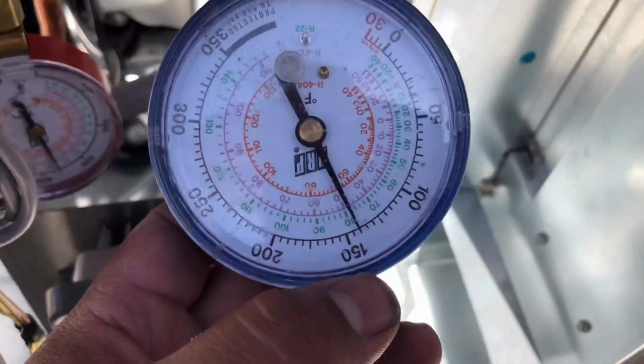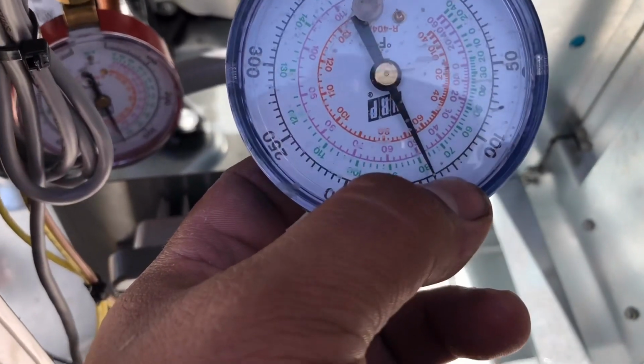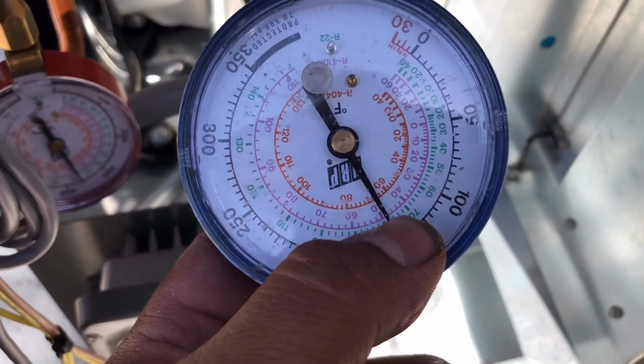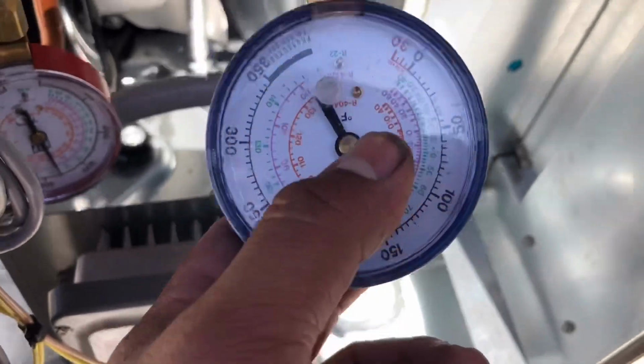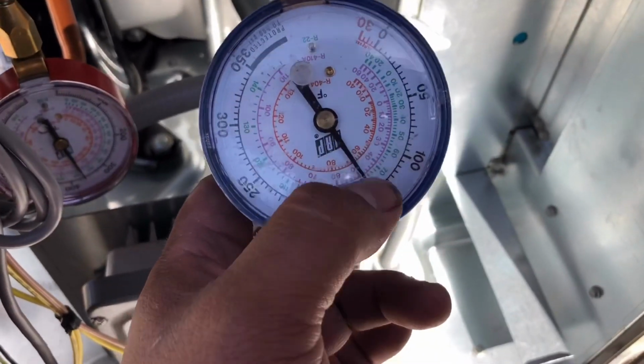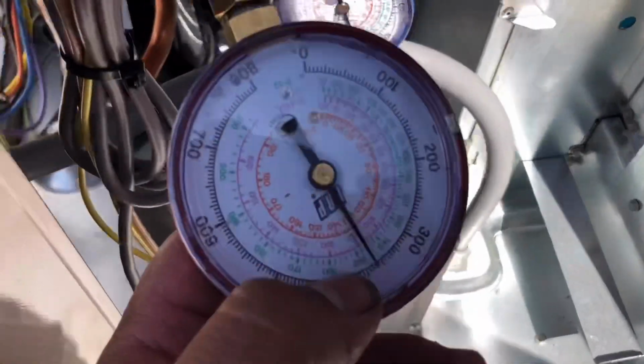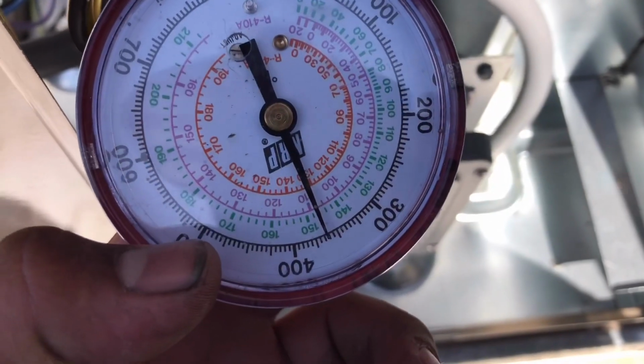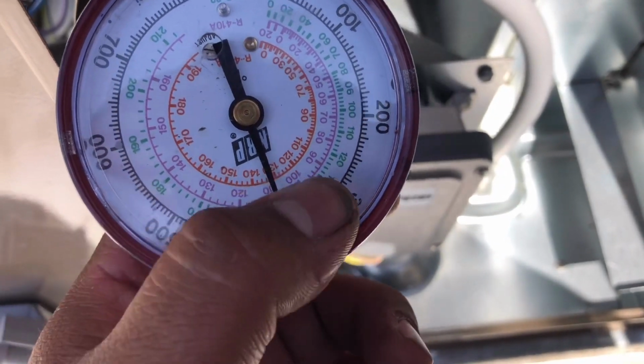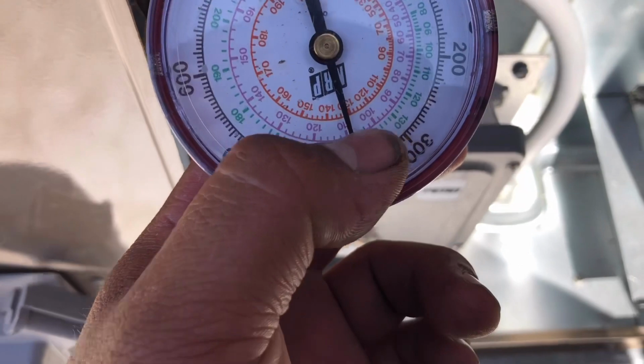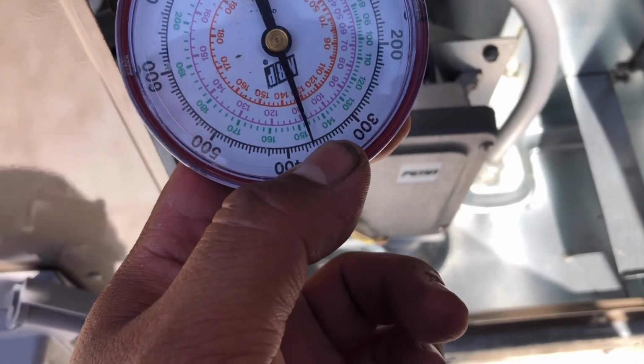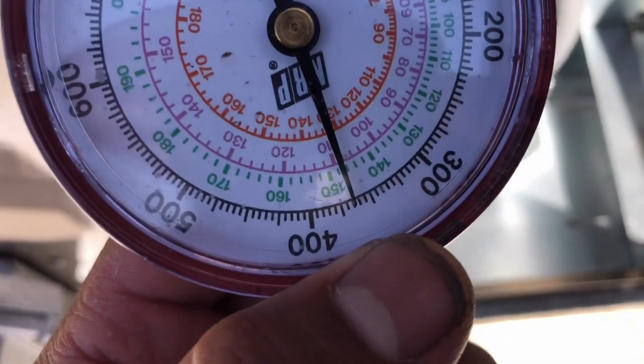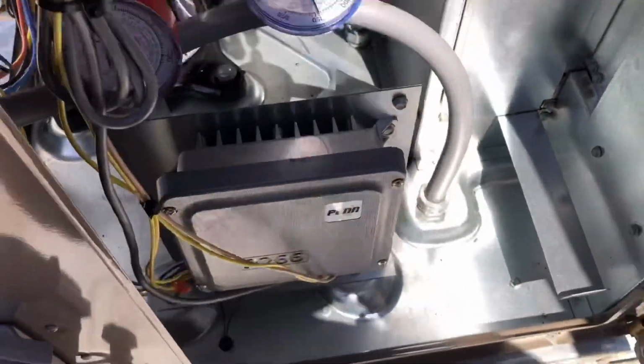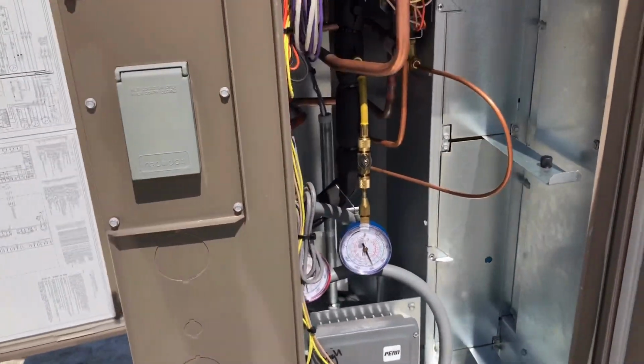Suction pressure is about 140, which is about a 50 degree, 48 degree coil. Makes sense, since it's really hot in the space, your suction is going to go up. Head pressure, we're looking at about 110, 108 or 110 condensing saturated temp, so about 365 psi. This just looks like it's running good, man.